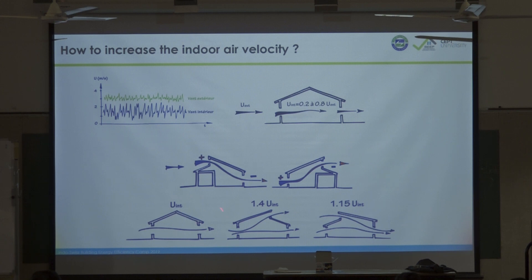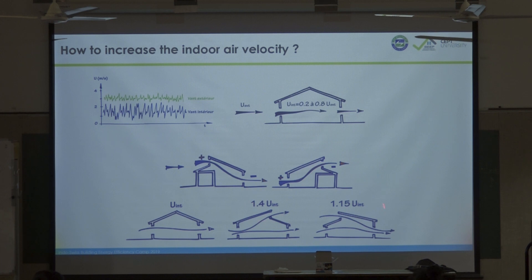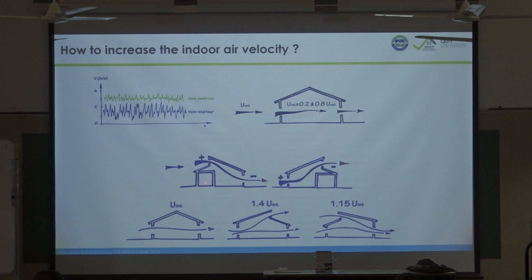When you do measurements on site — wind in green, indoor velocity in blue — there is always a difference, and indoor air velocity is always below the outdoor wind. However, you can accelerate the indoor air velocity with certain solutions: instead of a simple design, you can raise the opening area by creating a new opening and add 40 percent extra indoor velocity, compared to only 15 percent with another configuration.